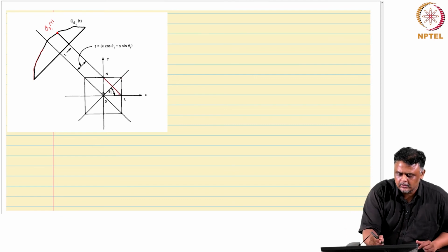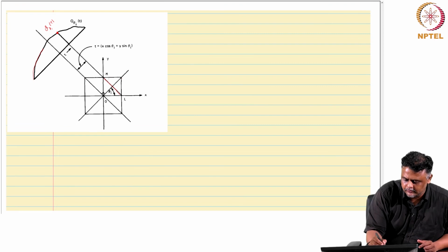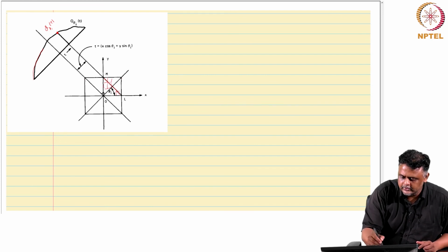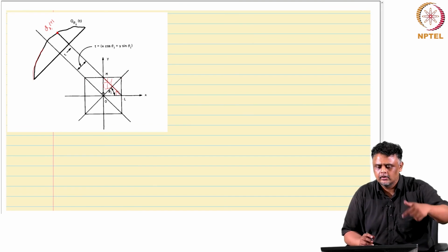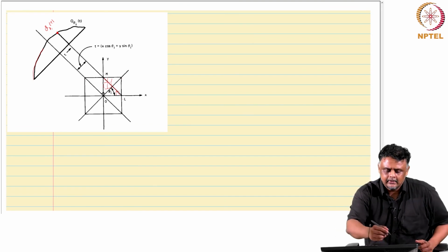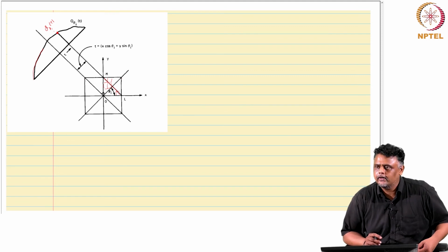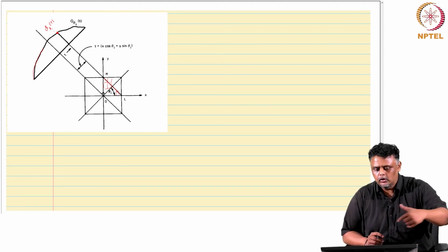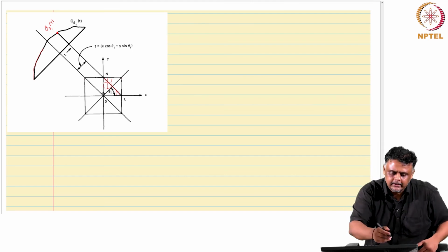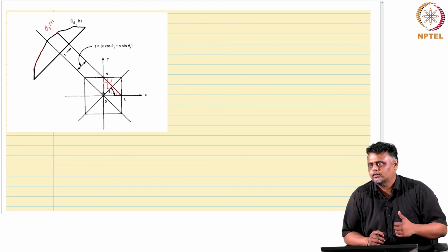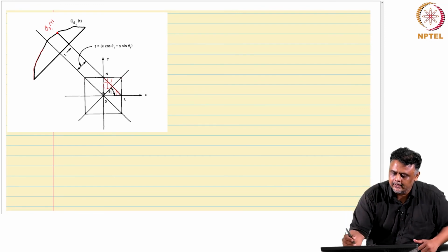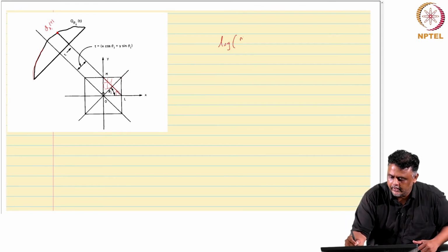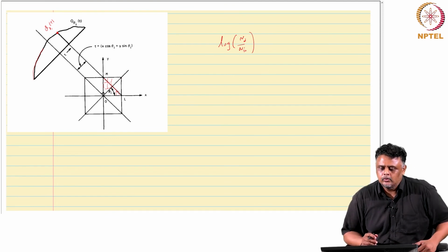What do I mean by smearing it across the grid? For the sake of this argument, there will be different image pixels at every point, so this line will go through different image pixels that you are trying to reconstruct. Wherever it cuts through an image pixel, you assign the same value q theta i of t to that pixel. You do that from every angle and sum them all up. This q theta i of t is actually called the filtered projection. So, you take the raw projection, which is your log data, the log of n naught over n from the previous slide, and you filter this.